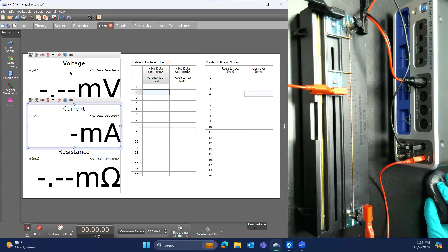The way this is set up on this screen, this voltage, it's what's being read by the voltmeter here. And then the current is measured by the signal generator's output. And then using those two measurements, we use a calculator equation here to apply Ohm's law, which is seen right here, to give us the resistance value that's measured at each incremental distance that we're going to be measuring.